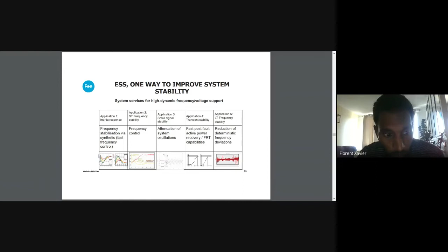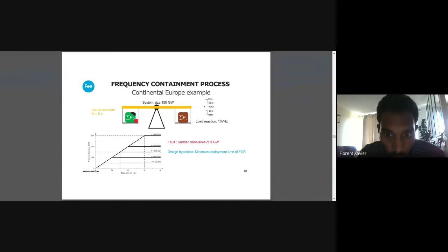So the next slide is about the frequency containment process. It's just an example that I would like to show about continental Europe, in a simple network and simulation with a system size of 150 gigawatt, an inertia constant of 5 seconds, and a load reaction of 1%. This system is what we use at the European level, and it's here to define the different frequency rules in continental Europe. We have a system with 150 gigawatt. We simulate a fault of 3 gigawatt, and we design the frequency containment reserve.